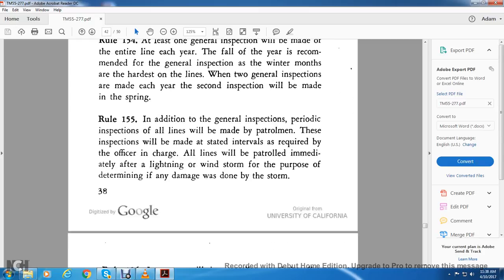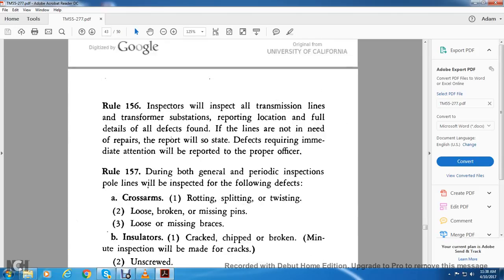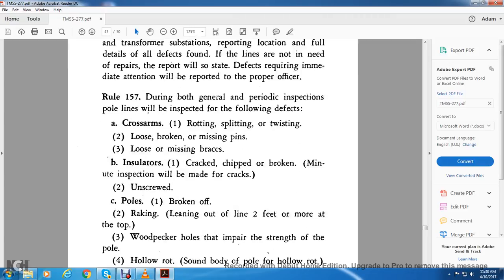Rule 155, in addition to the general inspection, periodic inspection of all lines will be made by patrolmen. These inspections will be made at stated intervals as required by the officer in charge. All lines will be patrolled immediately after lightning and windstorms, with the purpose of determining the damage done by the storm. Rule 156, inspectors will inspect the transmission line, transformer, and substation, and report in full the details of all defects found. If the lines are not needed for repairs, the report will state so. Defects requiring immediate attention will be reported to the proper officer.